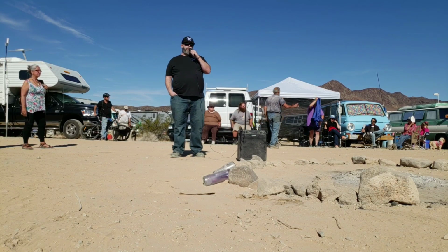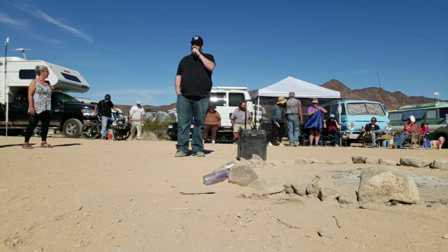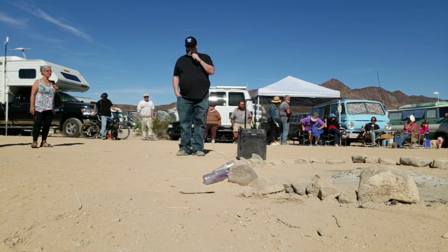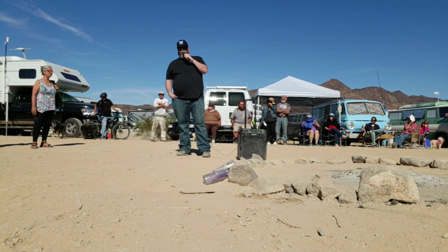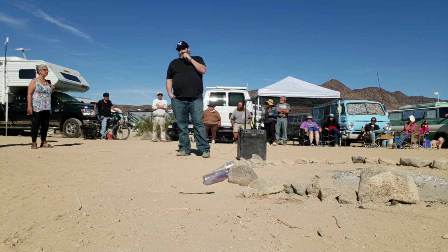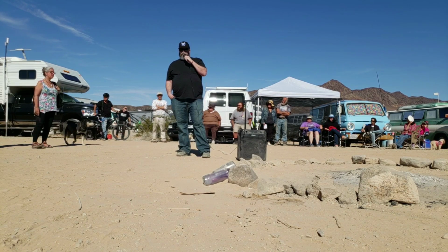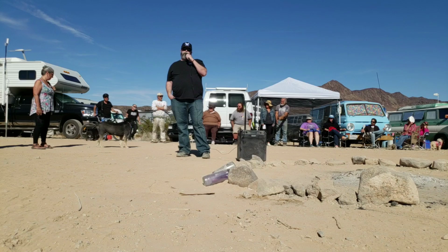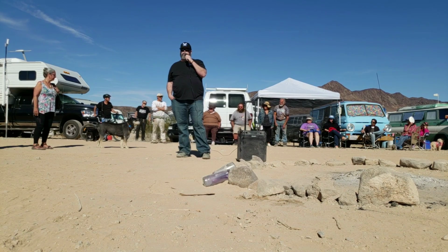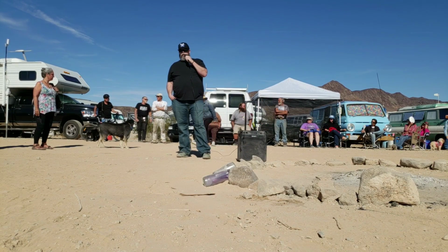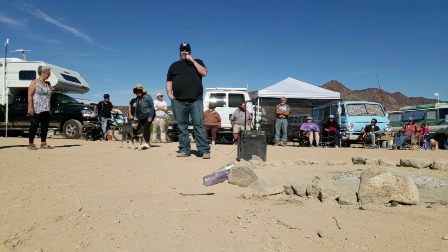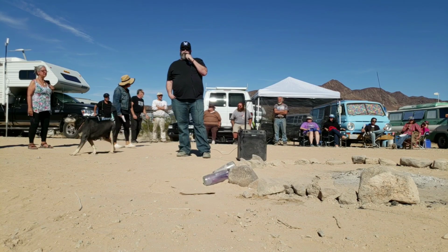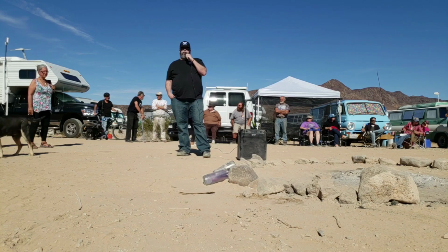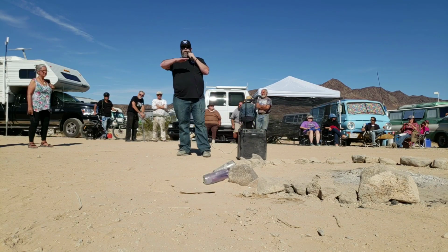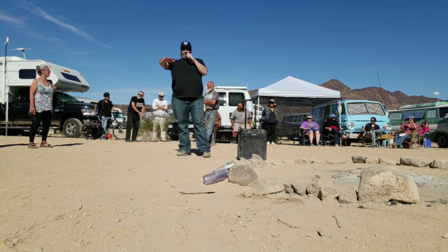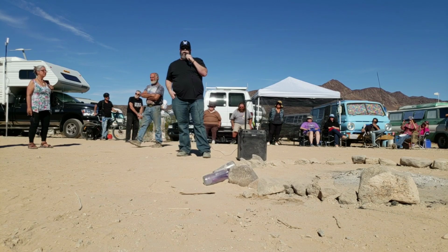So we did some testing on two 6-volt batteries. I'm sure someone here uses 6-volt batteries, right? Okay, so 6 volts are pretty popular, they have a reputation for lasting a little bit longer. We did two 6-volt tests on a 50 amp draw, which on a 12-volt system is about 600 watts. You could only get about 42 usable amp hours out of a 225 amp hour 6-volt bank before you got to 11.8 volts, which is where they say this is your 50% line, don't go below this or you'll exponentially reduce the cycles in the battery.